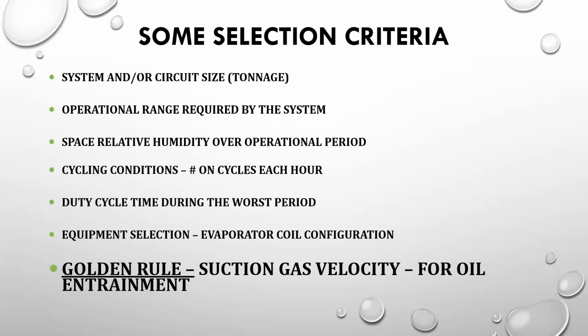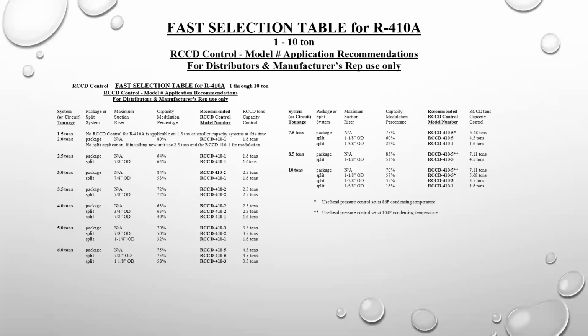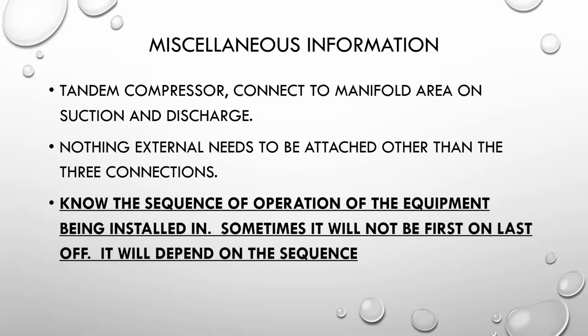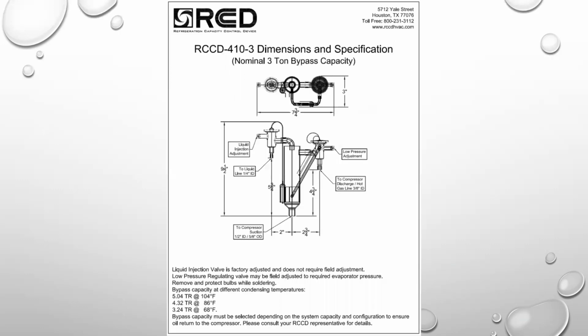On that previous screen, you'll see it says maximum suction riser. That is because we have to maintain 1,000 feet per minute in that riser. Miscellaneous information: tandem compressor connected to the manifold area. Nothing external. Know the sequence of operation. There is actually some equipment out there that brings on a very small first stage compressor, then shuts it off and brings on a larger second stage, then brings the first stage back on. In that case, you would want to put the control on that second stage.